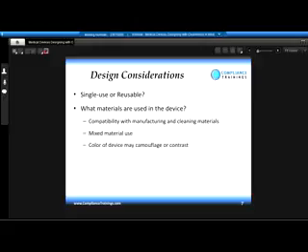In a lot of situations, the device isn't just made of one material, it's made of mixed materials. It has a polymer component as well as a metal component. In general, if it's just a metal component, it's going to be easier to clean than a mixed material device.